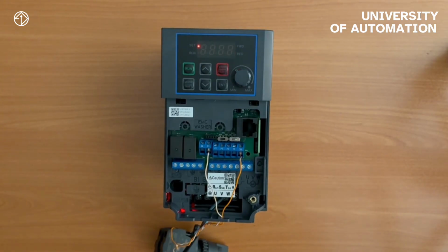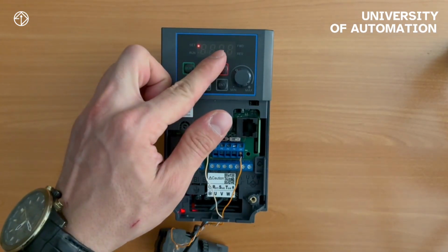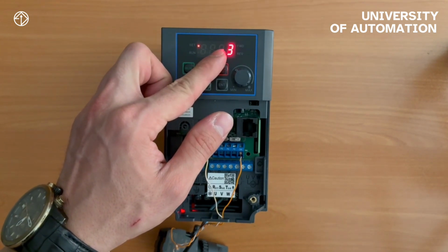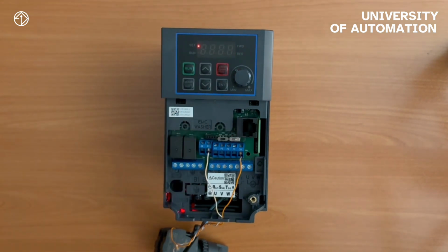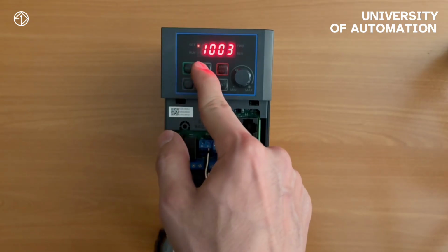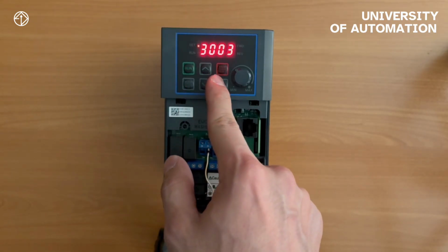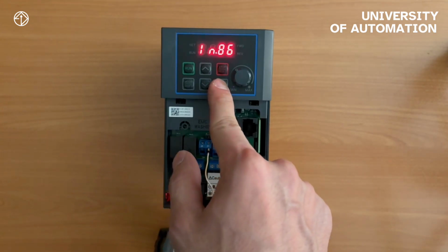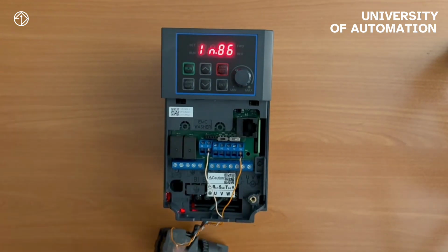Parameter 86 is for the delay when the digital input is about to turn off. So if you issue the command to deactivate the digital input, after the duration you set in parameter 86, your digital input will be deactivated. This is also set, for example, to 3000 milliseconds, which is 3 seconds.